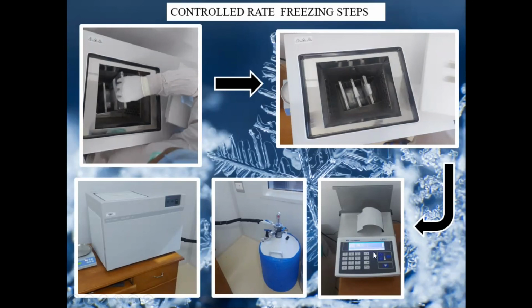At that time, what will you do? According to WHO, there are several guidelines. They say if any breakdown happens, you can immediately shift to -80 degrees Celsius. Or, if you have liquid nitrogen next to you, you can immediately shift the stem cell product to the liquid nitrogen. This is the 30-liter liquid nitrogen tank which is connected to the controlled rate freezer. The controlled rate freezer also requires liquid nitrogen.